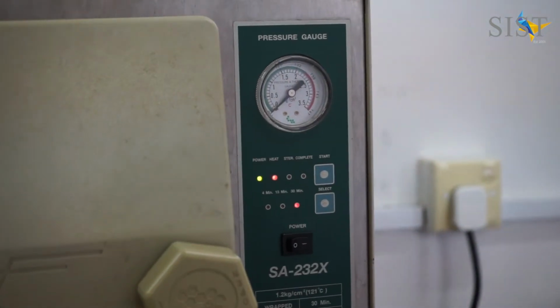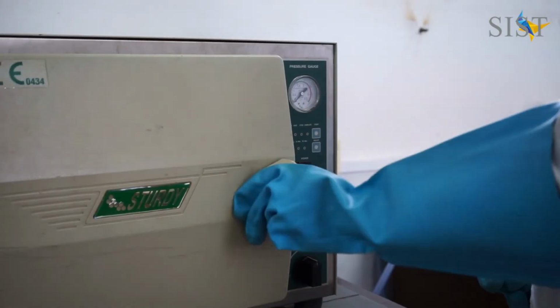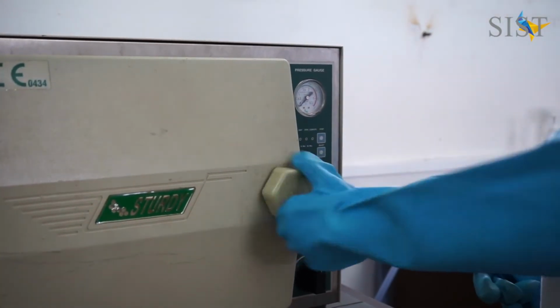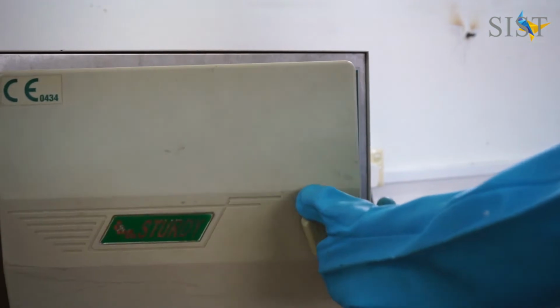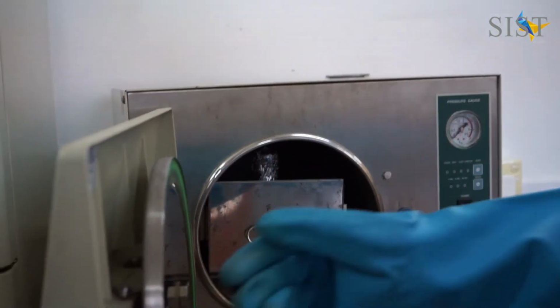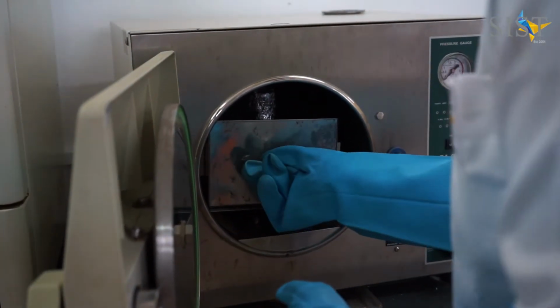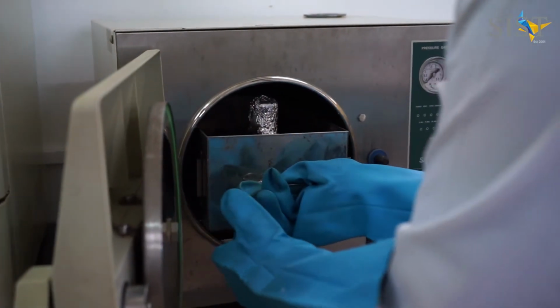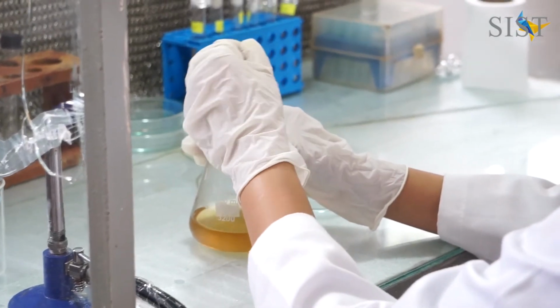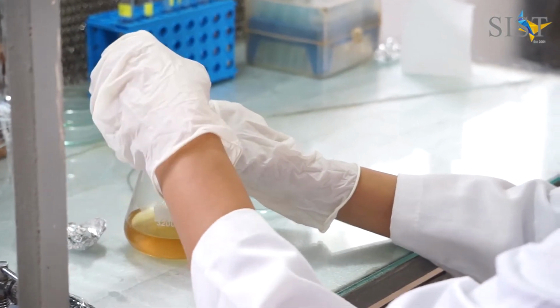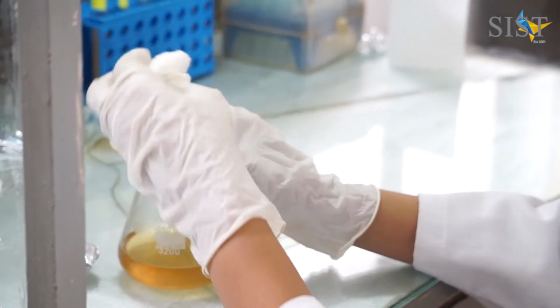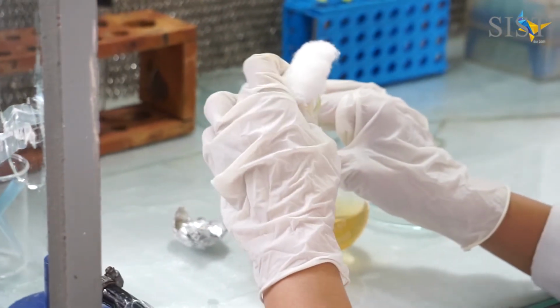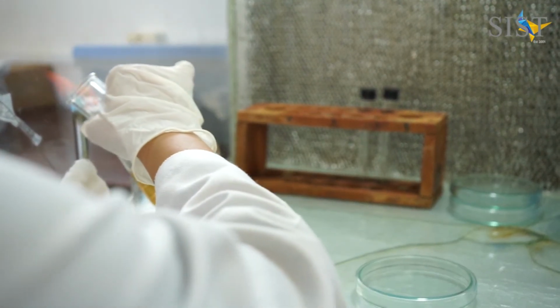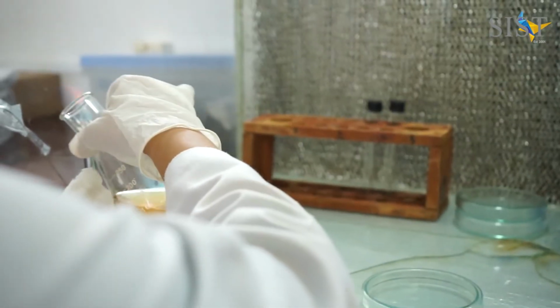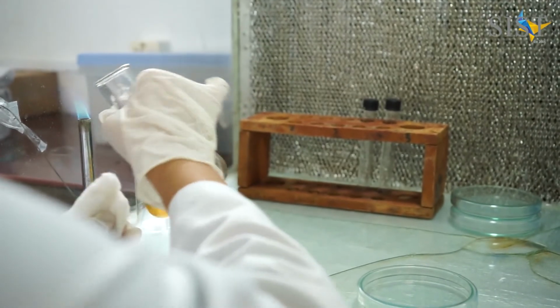Tighten the screw, and the operating conditions are usually 121 Celsius temperature for about 15 to 30 minutes. That depends on the type of culture medium. It reaches a very high temperature during that period. Once it is done, you have to wait until the pressure drops down to 0, and using protective gloves, you have to take out the autoclaved items.